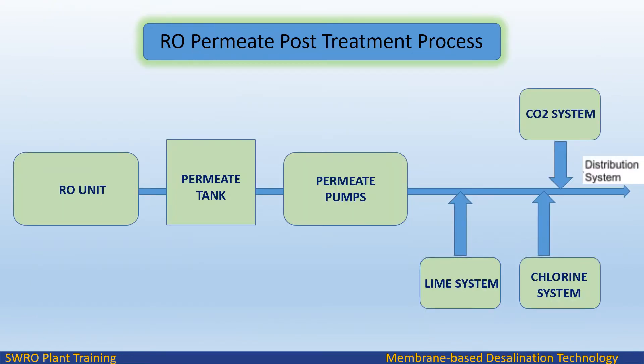Post-treatment is necessary to achieve desired product quality. Permeate water from RO units is stored in a permeate tank and distributed with the help of permeate pumps to the distribution network. The following dosing is performed: lime system, chlorination system, and carbon dioxide. Product water quality is maintained within limits after the post-treatment process.